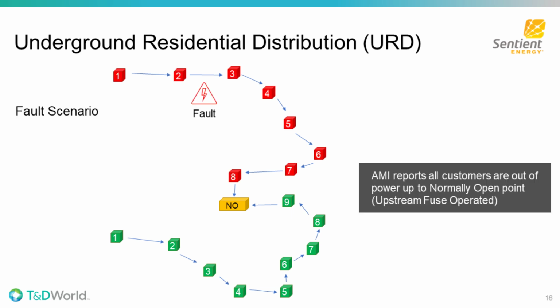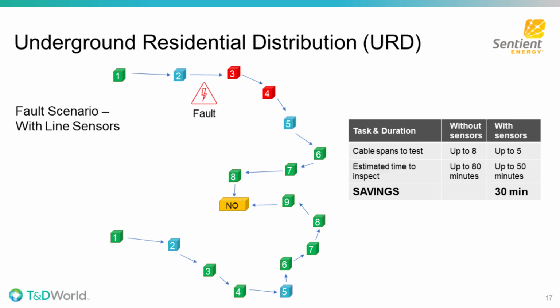Now, let's say we have a fault on the top section, okay? If AMI outage alarms are available, they're going to indicate that the top section is out, but we won't know specifically where the fault is. It could be on any of the 8 cable segments in the top section. Okay, on this slide, we've added line sensing, and we immediately know that the fault is between cabinets 2 and 5. So there are only 3 possible cable segments where the fault could be instead of 8.